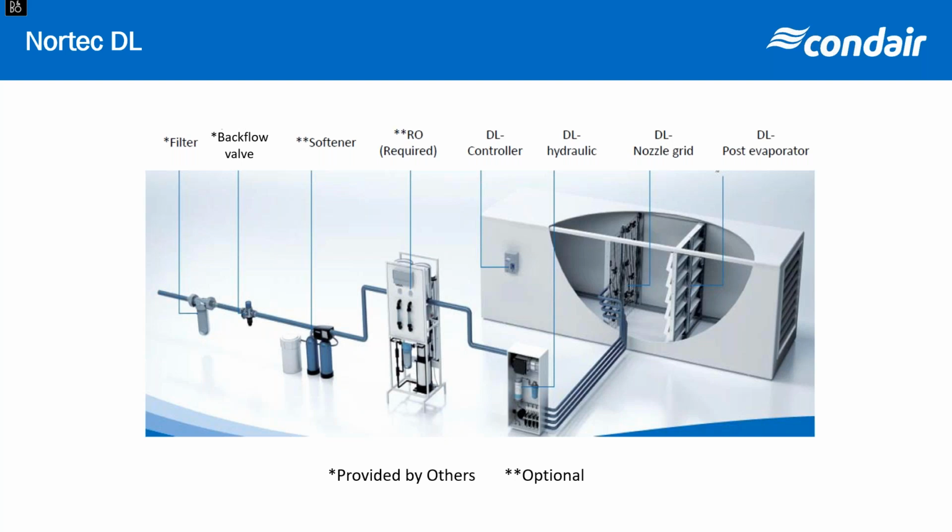So if we were looking at this moving from left to right, the airflow would be coming from your left to the right. That section right there between those 2 banks, we have on the left a bank of nozzles, and then we have a media pad. It's made of ceramic. There is really no maintenance to do with any of that. It's only a 2-foot section, as Nathan is showing there. But in all, for door access and other things, we would require an extra foot on each side, so about 4 feet.